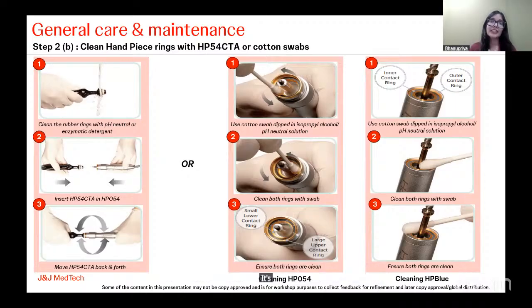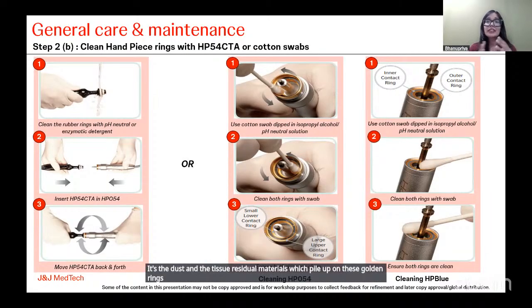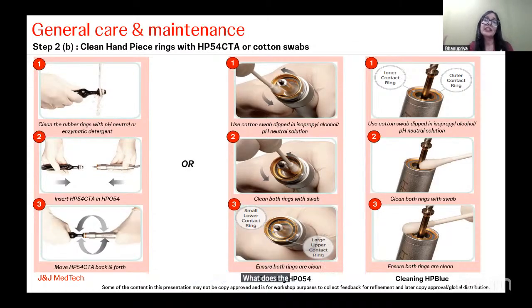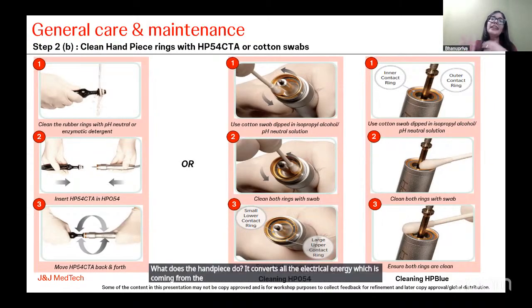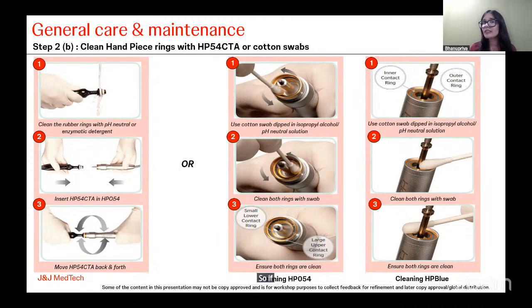It's the dust and the tissue residual materials which pile up on these golden rings, which will prevent the flow of current from the generator to your probes. And handpieces are very, very important. What does the handpiece do? It converts all the electrical energy which is coming from the generator into mechanical energy and throws that mechanical energy into the harmonic end effector or the harmonic probe. So if your handpiece is not working well, your probe will also have problems in working.